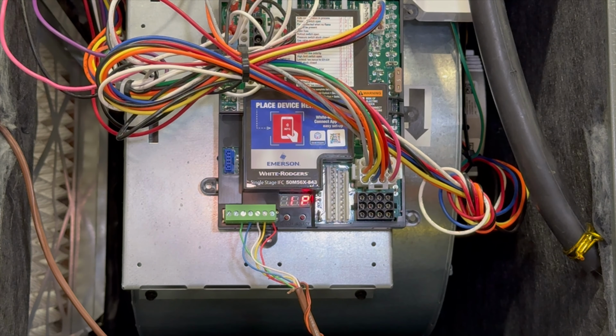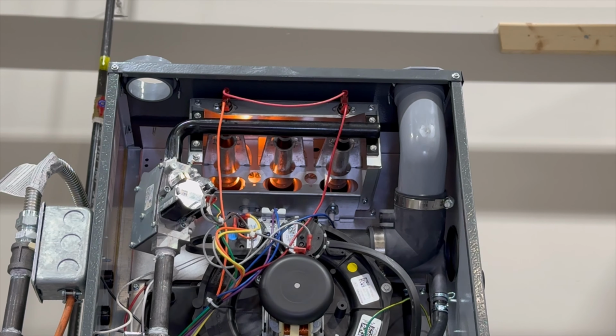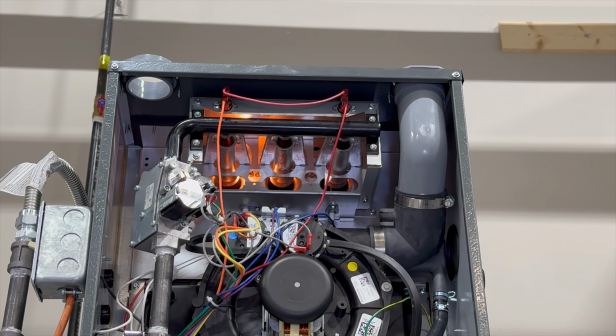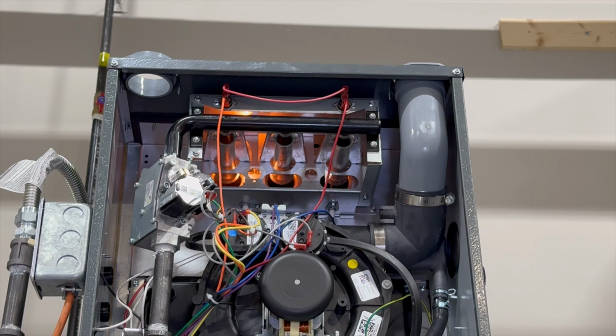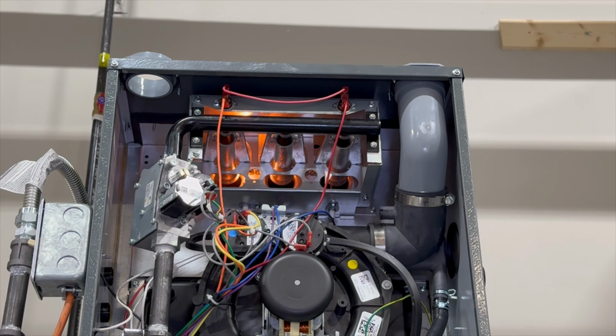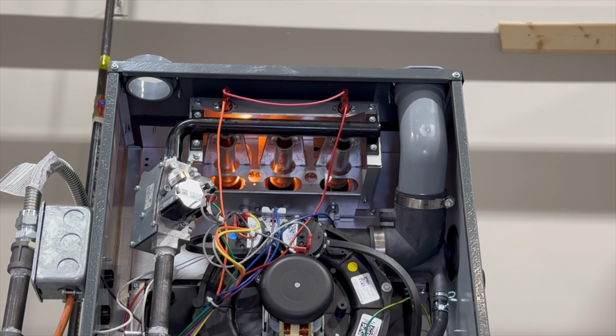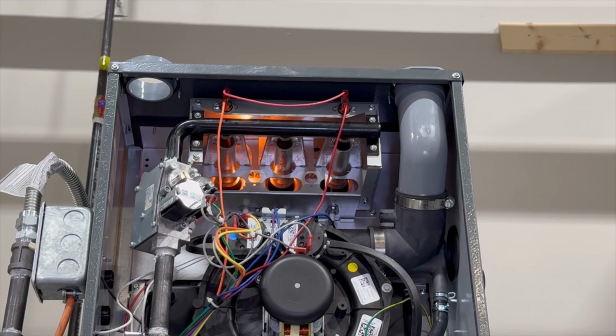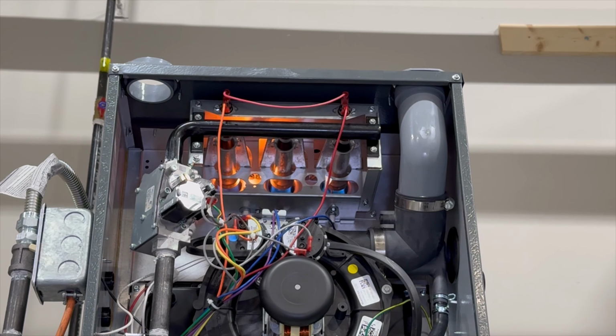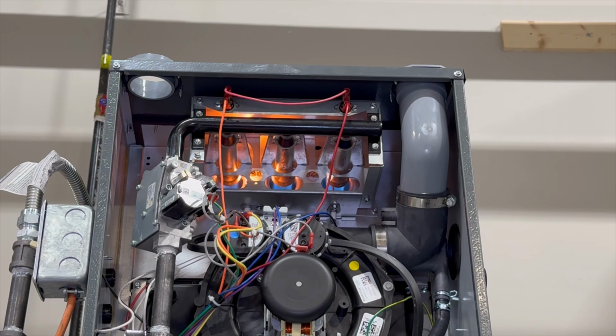Should the flame not immediately show, the furnace will go into IP, or inter-purge, which is a purge cycle to verify no raw gas is left in the furnace when it tries to reignite. After that 20-second inter-purge period, or whatever inter-purge period is set on the control, it will try to ignite again.